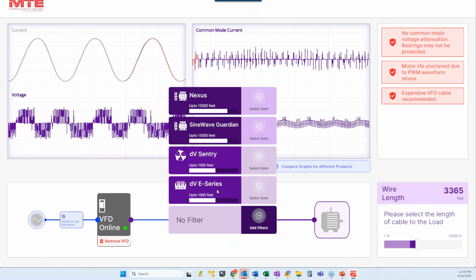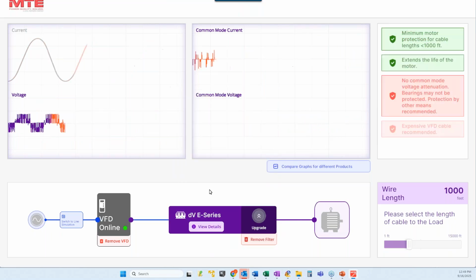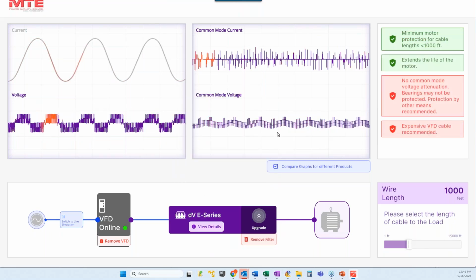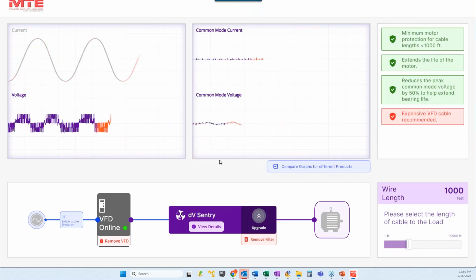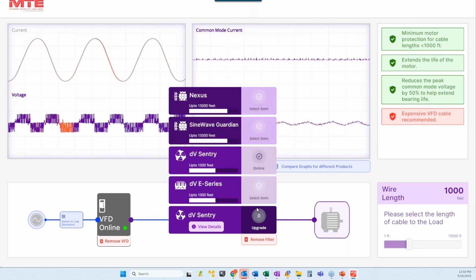And MTE's got 4 different types of filters, dV E-Series filter. This is good for up to 1,000 feet. Less than 1,000 feet extends the life of the motor. No common mode voltage attenuation. Expensive VFD cables recommended. Go to the Sentry product. You can see that really does a good job. So depending on your length and what your application is, you can go to something like that.